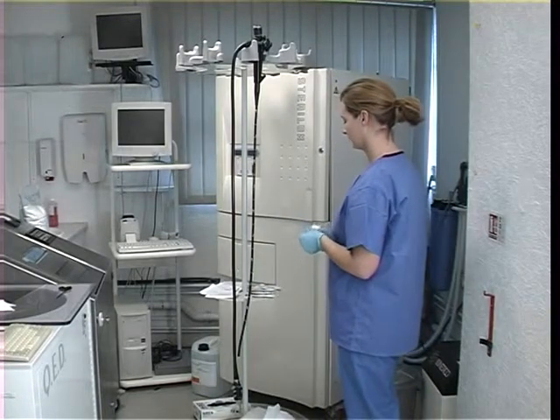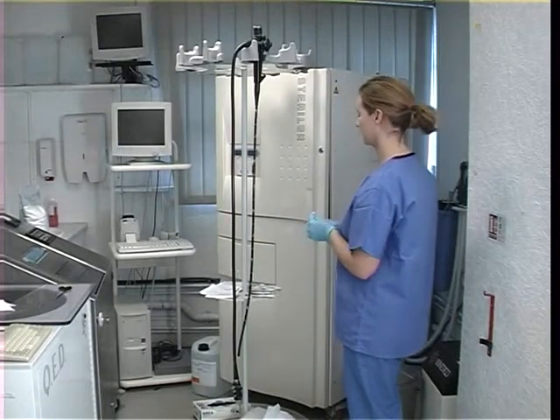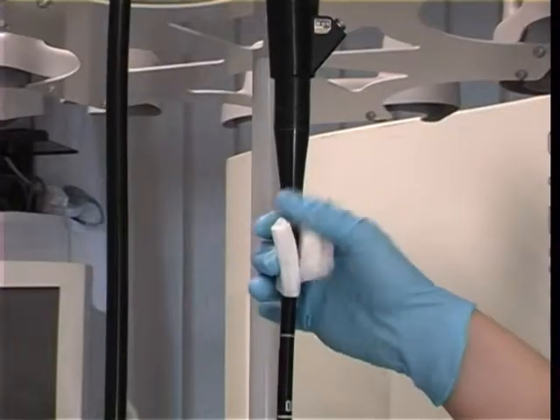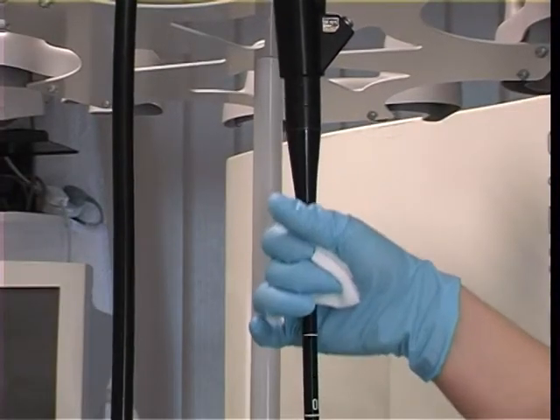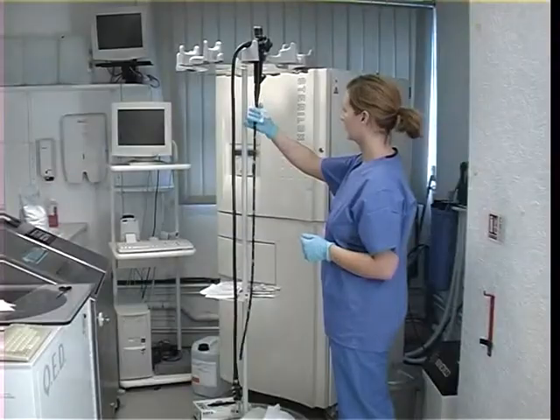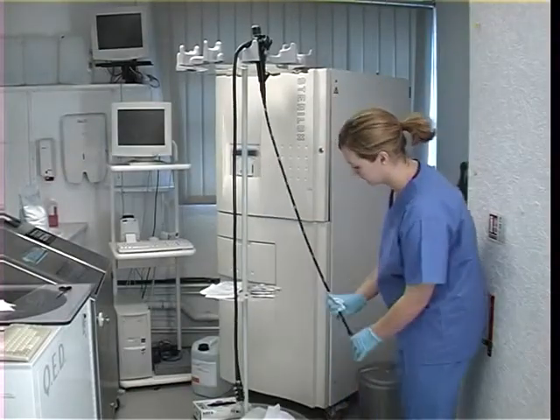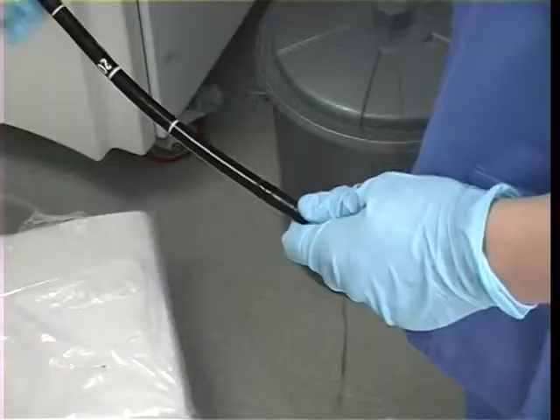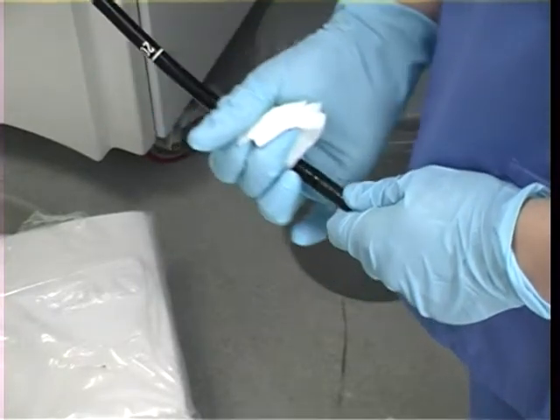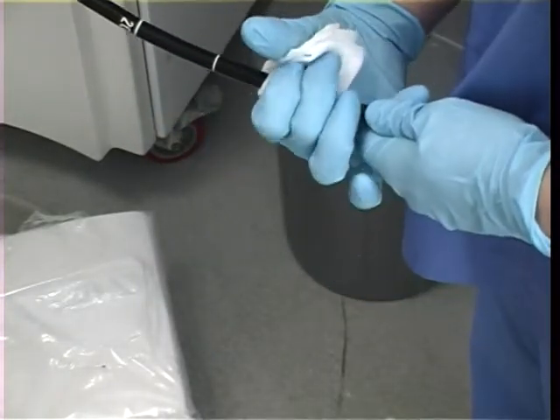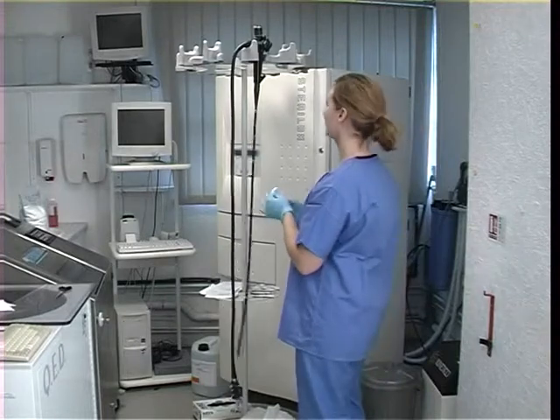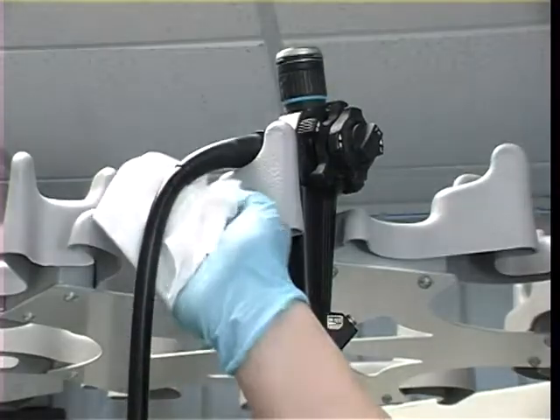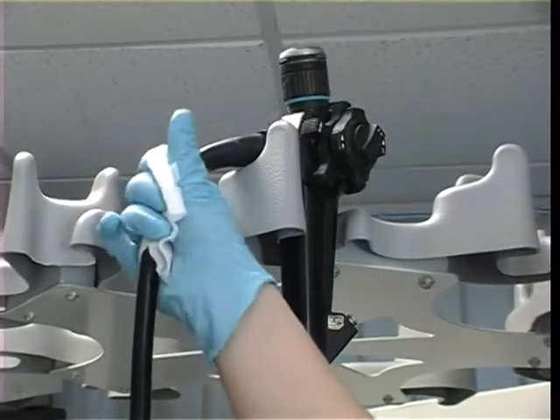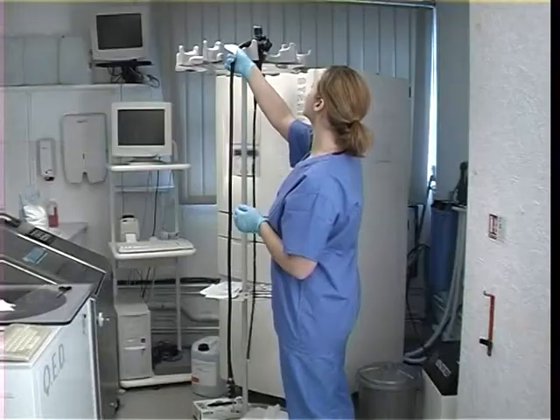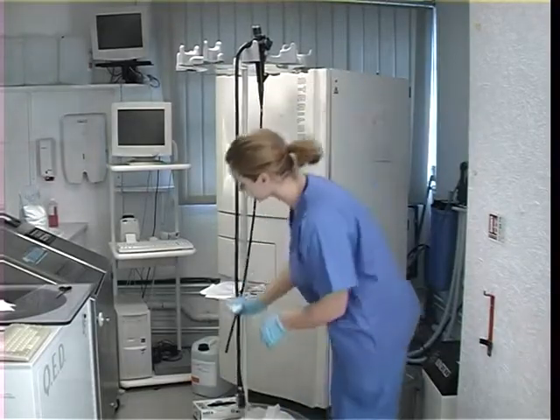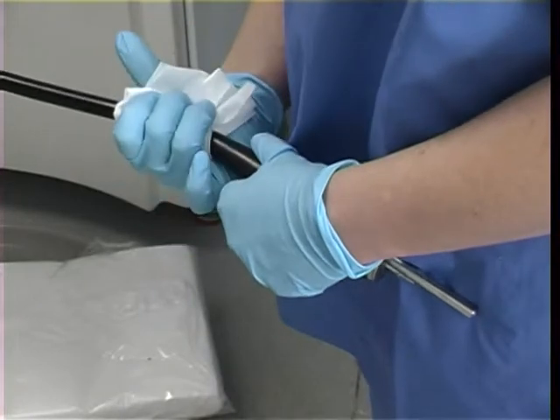Start by applying the wipe under the boot on the light guide insertion tube using one circular movement. Then continue to wipe the complete length of the tube in a straight downwards wipe, finishing off just above the distal end bending section where once more you will apply using one circular movement. Turn the wipe over in your hand and then continue to use the same application technique to apply the wipe from below the boot on the control head junction to below the boot at the light post end.